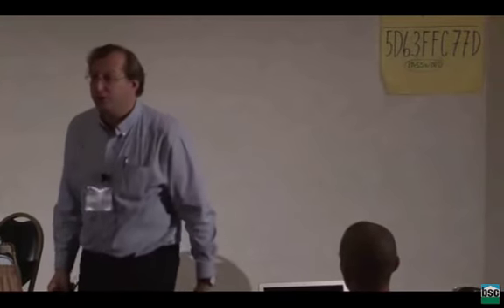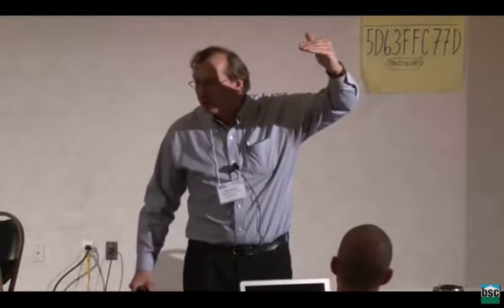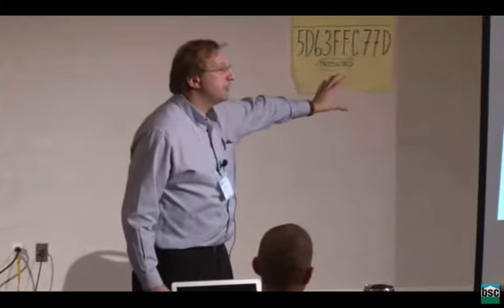But there's some other systems. You can get this type of a system from Fujitsu. You can get it from Mitsubishi. You can get it from, in this case, here's an LG. I thought they had the nicest drawings, so I showed you them next. But you can't buy any of them here. So they're all low load capacity. They're variable output, so they can slow down the compressor when you don't need a lot of heat and speed it up when you really do. And they use water as a medium so you can store it and make both domestic hot water, space heat, and space cool. So we're getting closer to the magic box. It's just that water is in the way. Yeah, all that water between us and them.